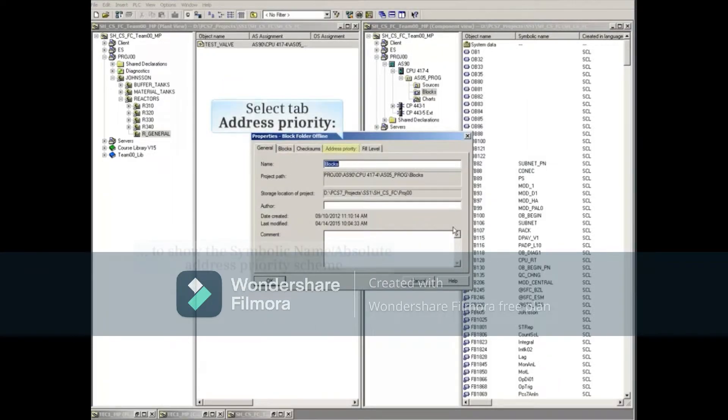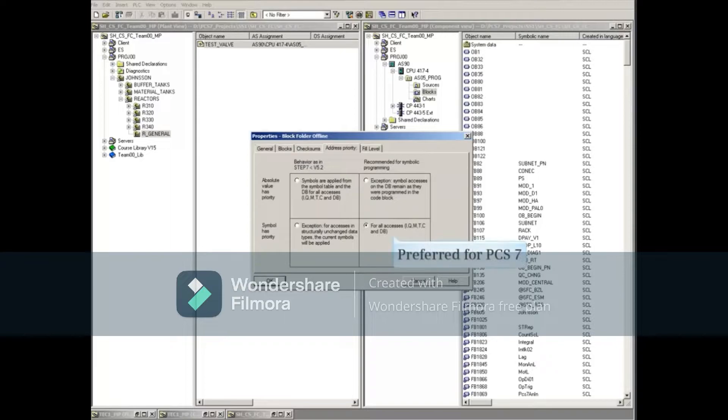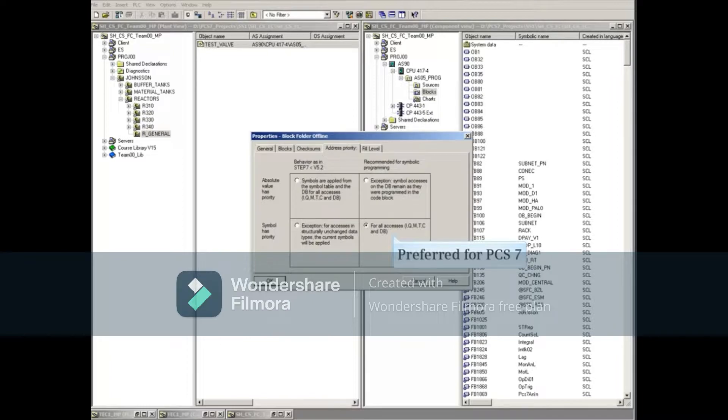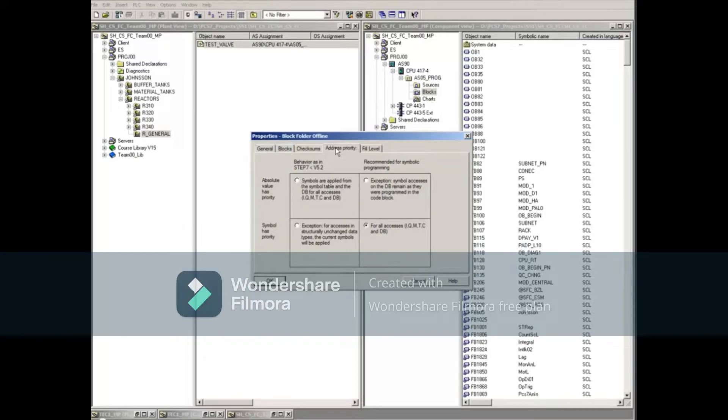Select the Address Priority tab to show the Symbolic Name Absolute Address Priority Scheme. Verify that the bottom right box is checked, placing priority on symbolic names. This setting guarantees that the symbolic names in the charts won't get lost if you delete a symbol to move it to another channel. When done, close the window.